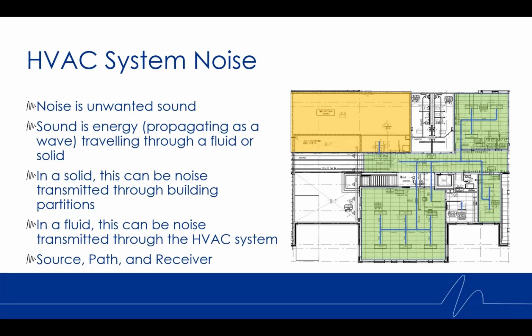What's important to remember here is that in any of these scenarios, whenever we talk about noise or sound, we're always going to talk about three separate aspects. We have the sound source, we have the sound path, and then we have the receiver. The image on the right here is a typical school layout. The yellow box is a mechanical room. It has several pieces of mechanical equipment in it. The blue lines leading out of that yellow room are the duct paths. That's the path that the sound is traveling from that unit into the different rooms. The receivers are going to be the people within those rooms that are experiencing the noise that has traveled through that duct.